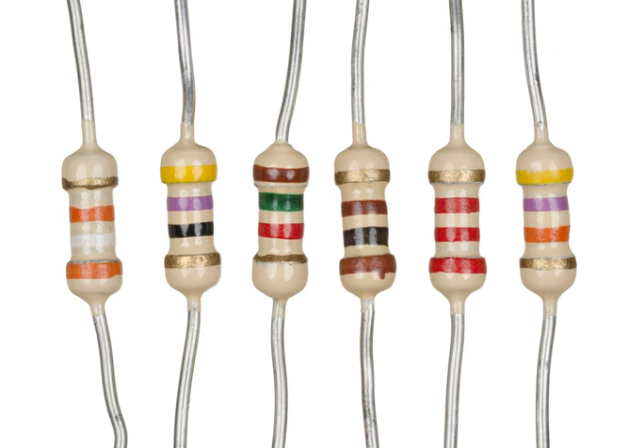Topic: resistance decade boxes. A resistance decade box or resistor substitution box is a unit containing resistors of many values, with one or more mechanical switches which allow any one of various discrete resistances offered by the box to be dialed in. Usually the resistance is accurate to high precision, ranging from laboratory, calibration grade accuracy of 20 parts per million, to field grade at 1%. Inexpensive boxes with lesser accuracy are also available.